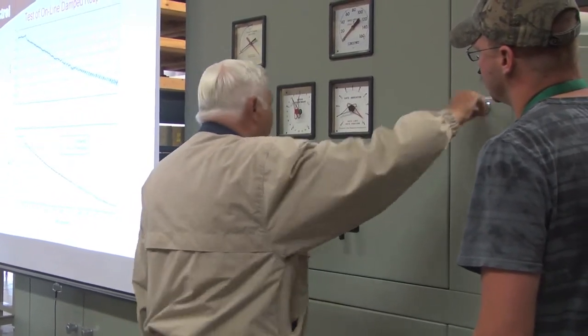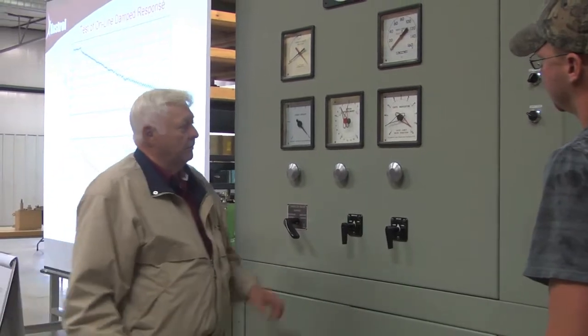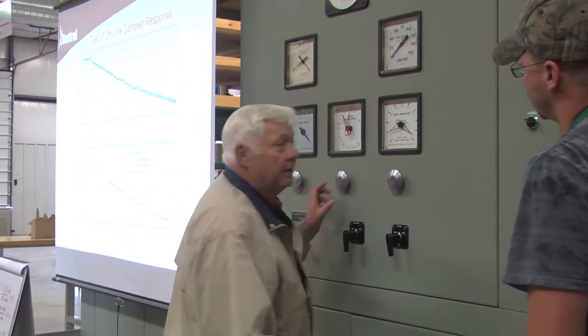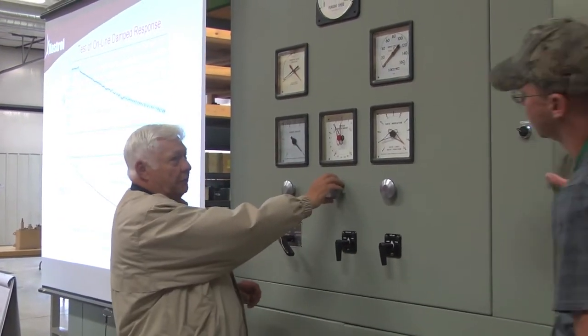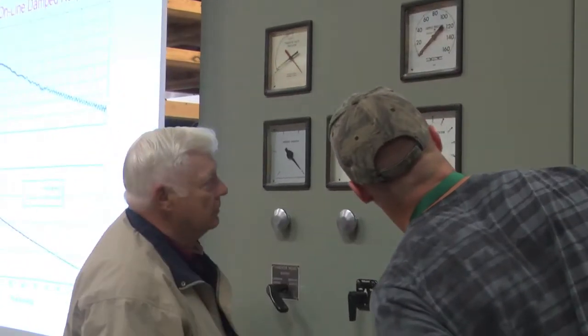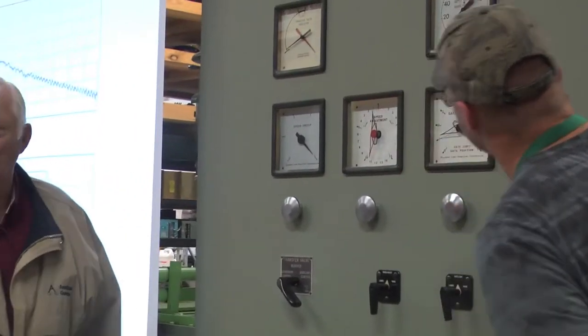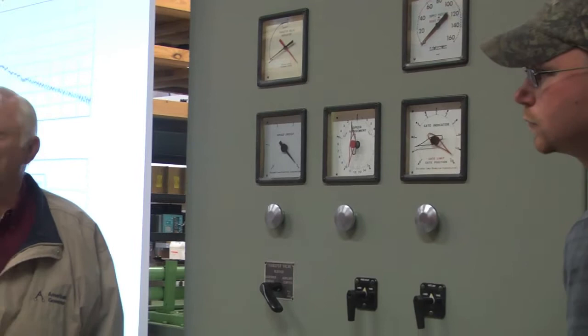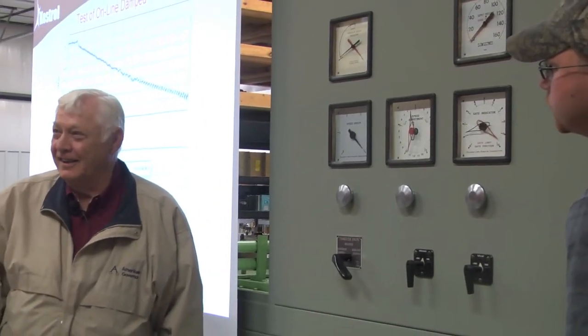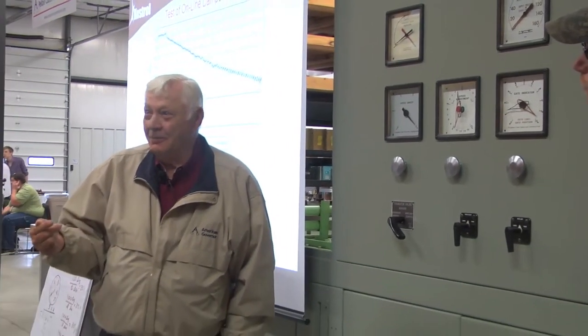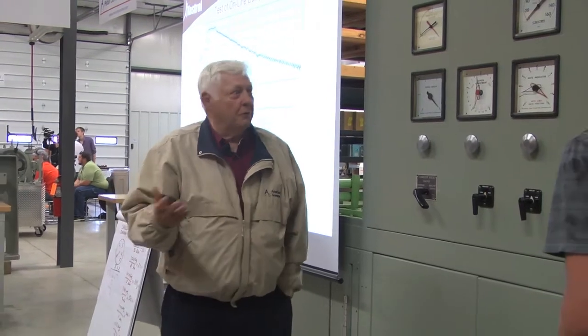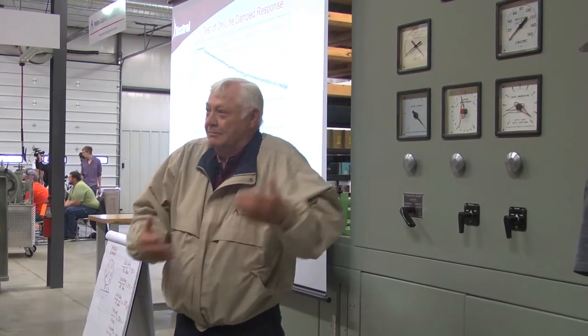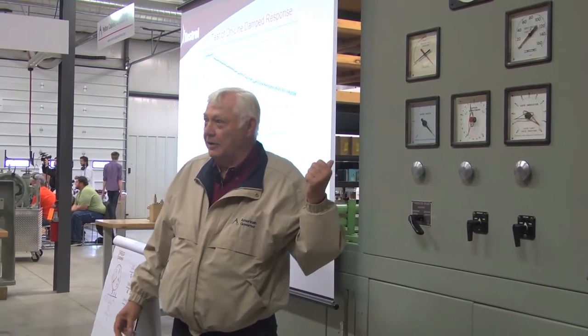So it's pretty close. So now, okay, I'm at 9%. Somebody watch real close. 12. So it moved 3%. 1 divided by 3 is 33 1/3. Your temporary droop on this unit is 33 1/3%. So now I know how much gain I got for temporary gain, okay?